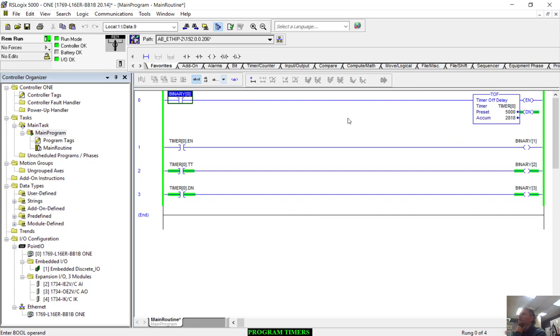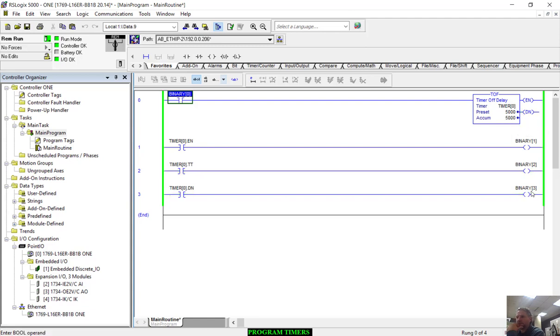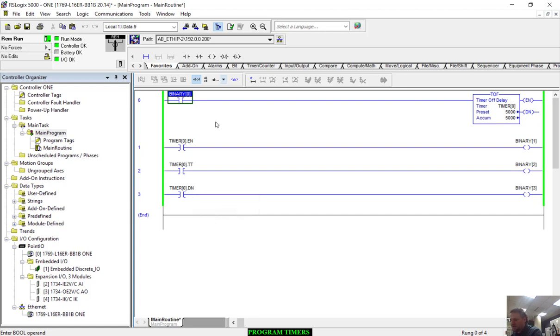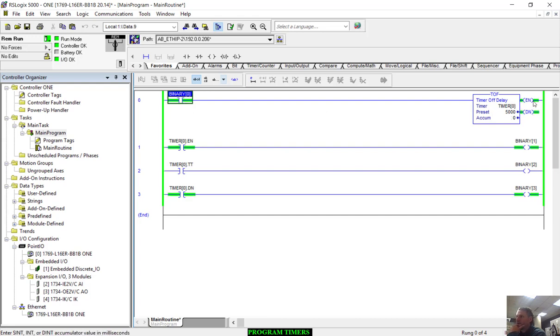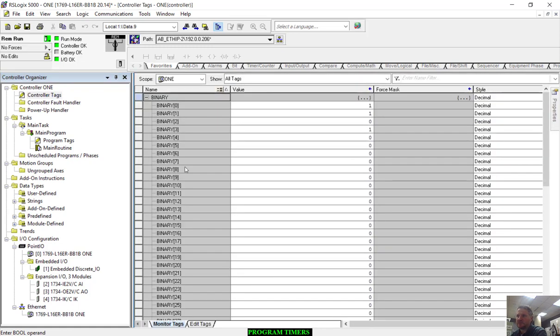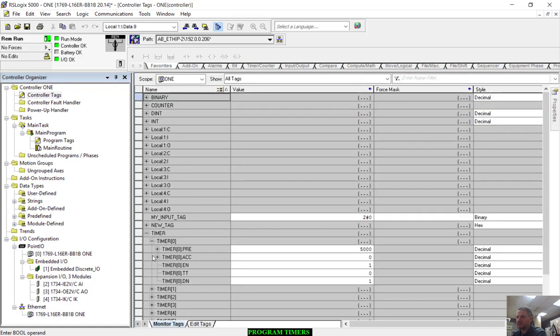It's not until I turn it off that we see it starting to time. And as soon as it's done timing, all the bits turn off. Notice the enable's off, timer timing is not timing, and the done bit is no longer on. Let's try that again and watch it a lot closer. I'll close this contact. I see enable and done on. You see these two bits here on.